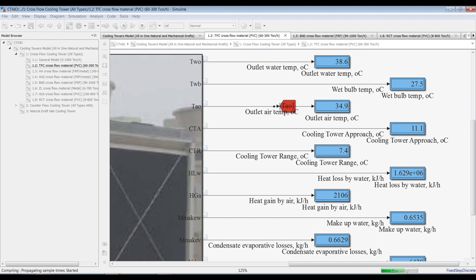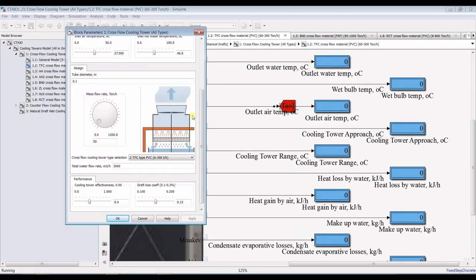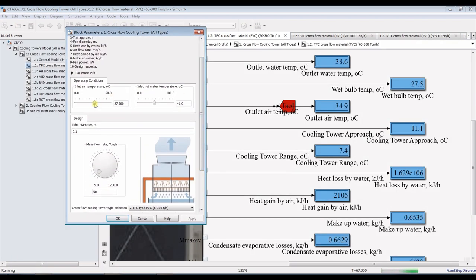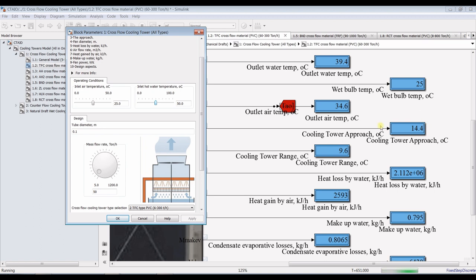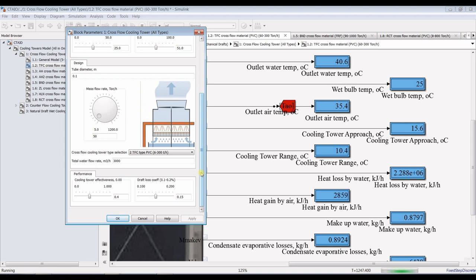Let's see our changes. I will change the inlet air temperature — suppose I would like to decrease inlet air temperature down to 25°C — while increasing the inlet hot water temperature up to 50°C. As you can see here, the changing in approach and water cooling range — it depends on your design, which design you would like to prefer, which is the most efficient one you would like to change.